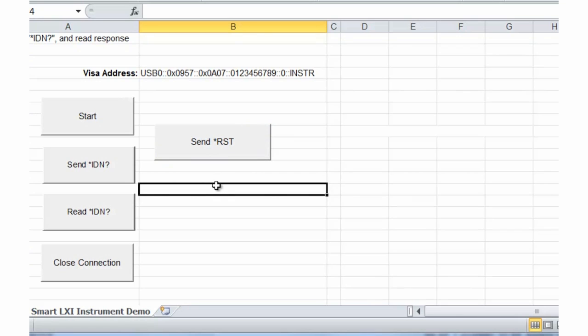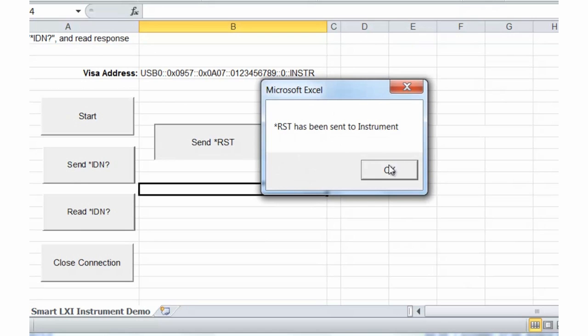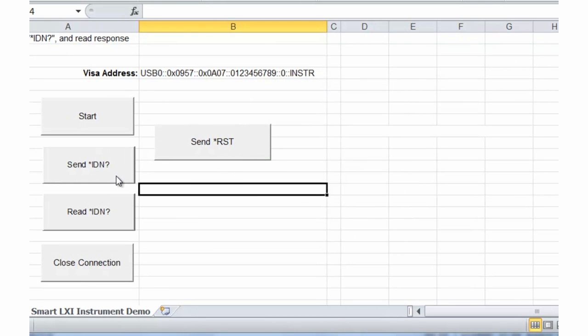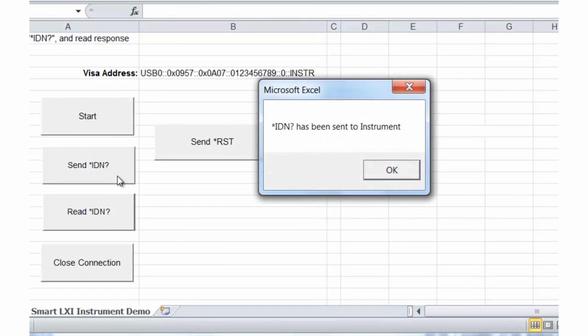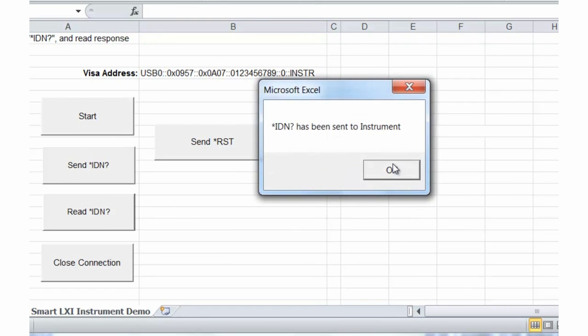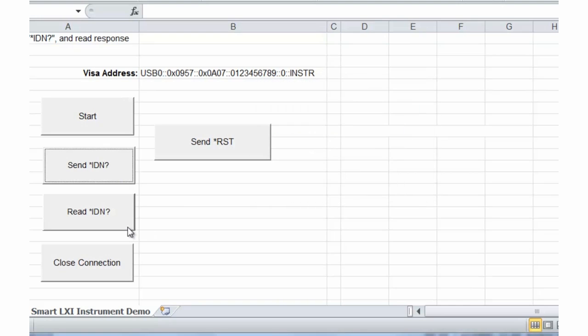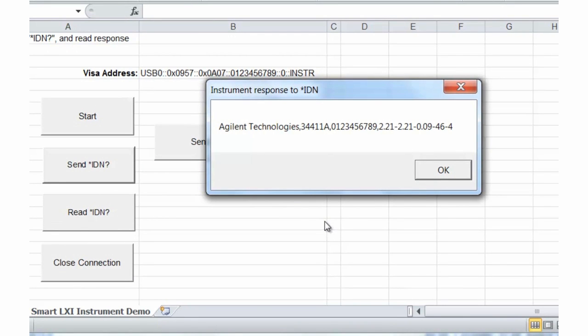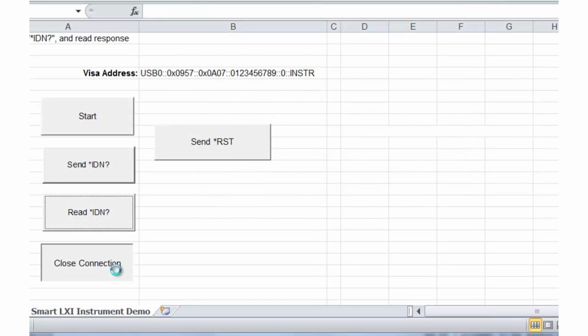Now we can go ahead and run our program. We'll start it — we've initialized our variables and opened our resource manager. We can send the reset command, and it says the reset command has been sent. We'll send our *IDN command, then read back the response — there's a response back from the instrument. And we'll close our connection.